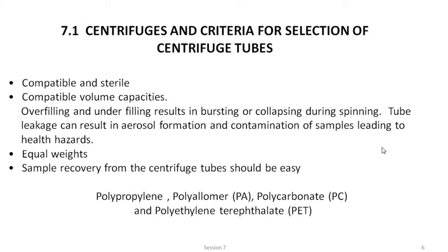They should be of equal weights. This is very important because just recall your childhood game wherein two of you catch hands and go round and round. Okay, so if the opponent is lighter than you, what will happen? Or if he is heavier than you, what will happen? So here you have to bear in mind that the centrifuge tubes should be of equal weights and hence the capacity should also be equally full.